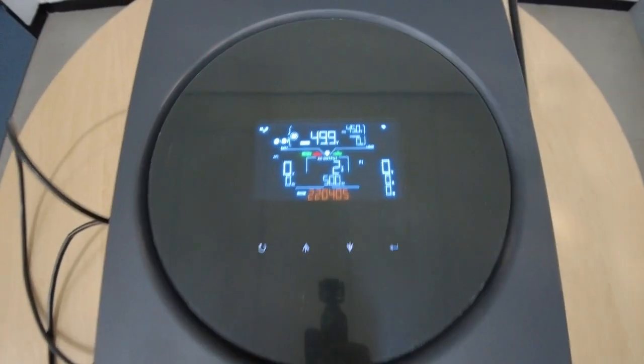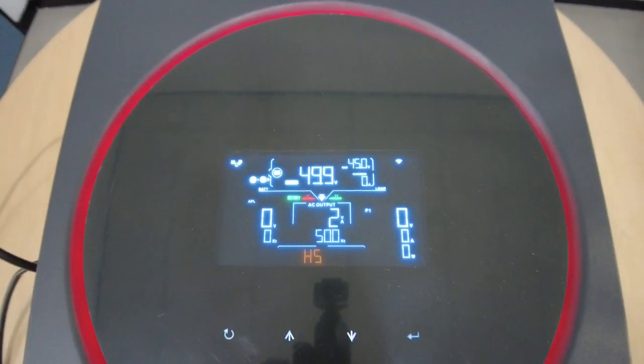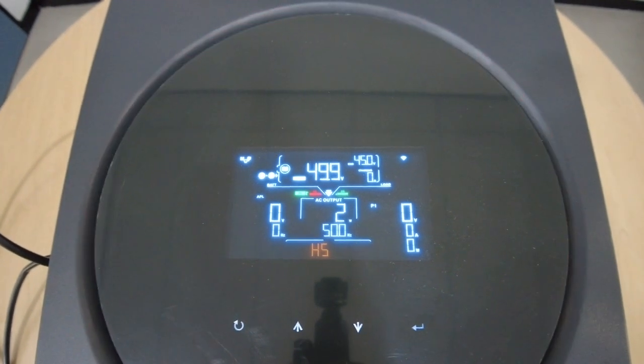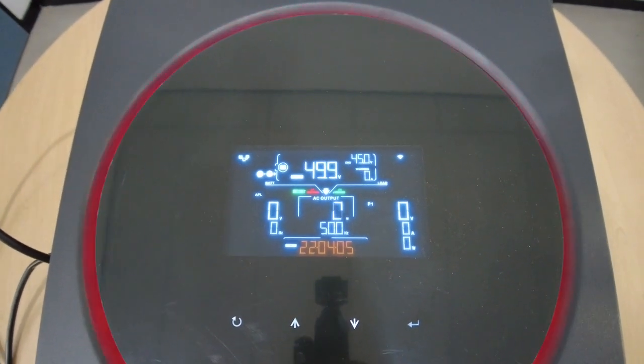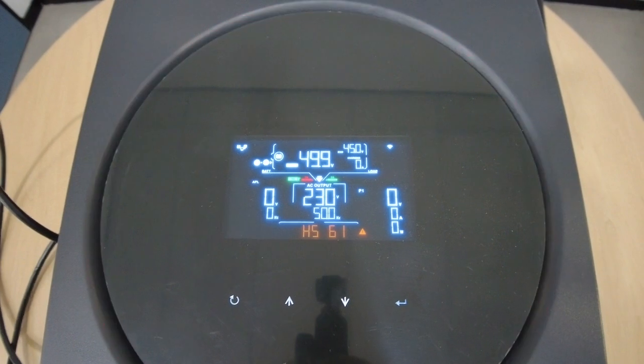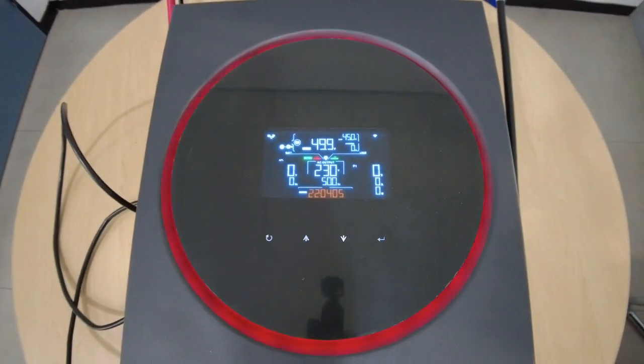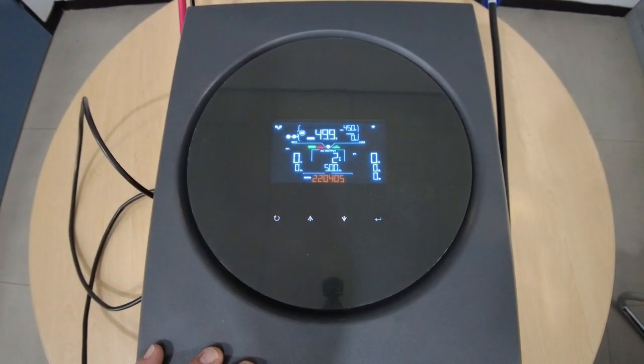5. As you can see, the inverter just came on with a H5 warning. That is your telltale sign that communication is not established. The inverter is warning you there's no communication between the inverter and the battery.